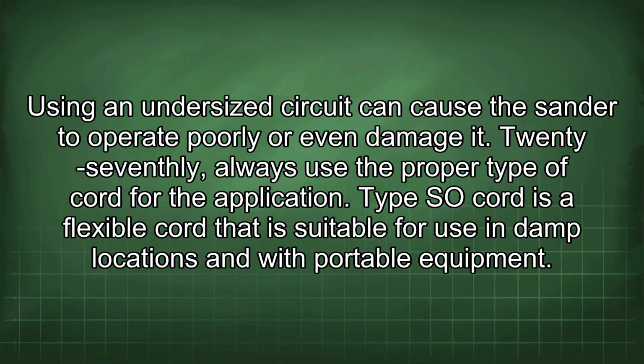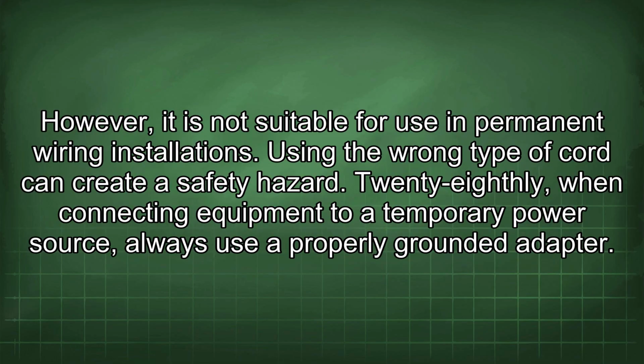27thly, always use the proper type of cord for the application. Type SO cord is a flexible cord that is suitable for use in damp locations and with portable equipment. However, it is not suitable for use in permanent wiring installations. Using the wrong type of cord can create a safety hazard.